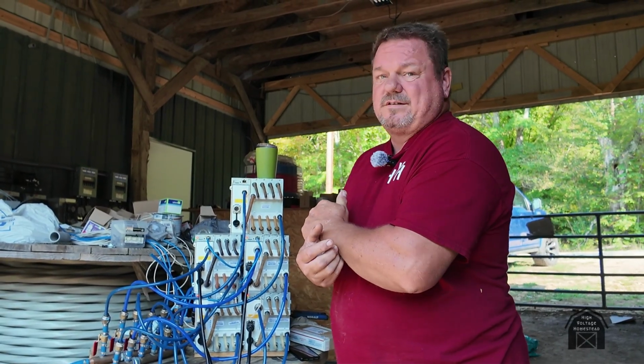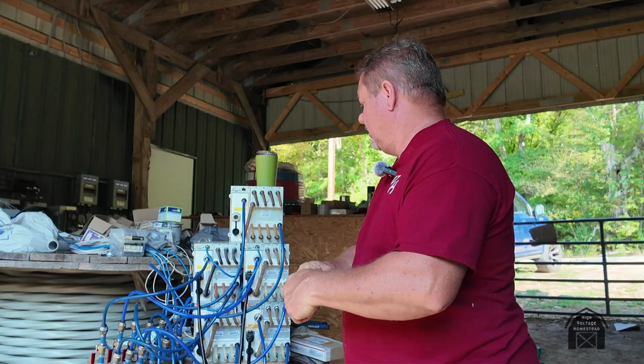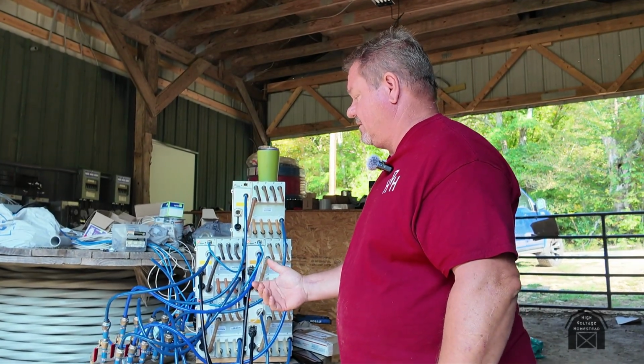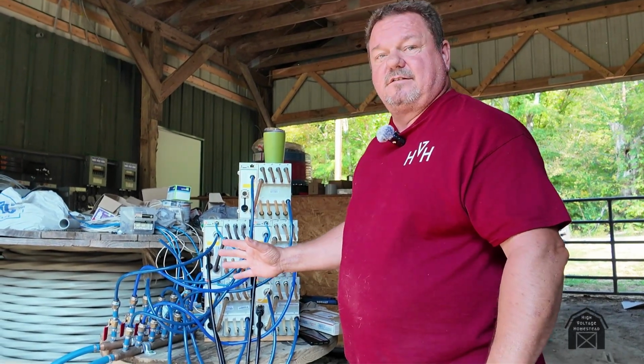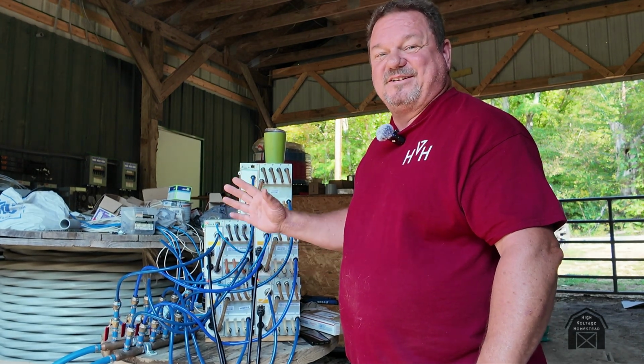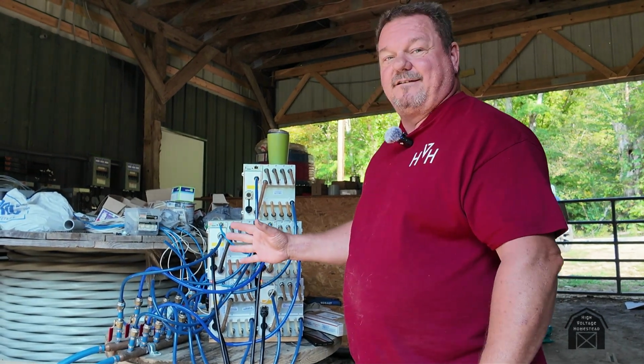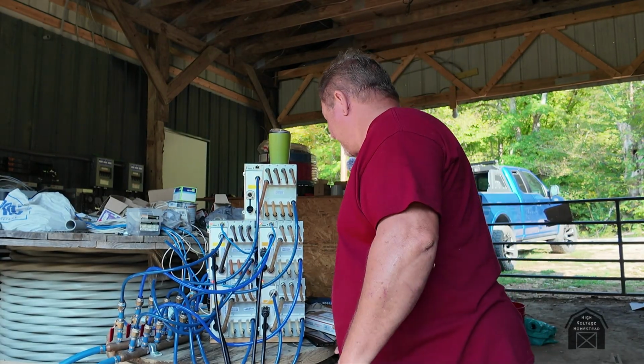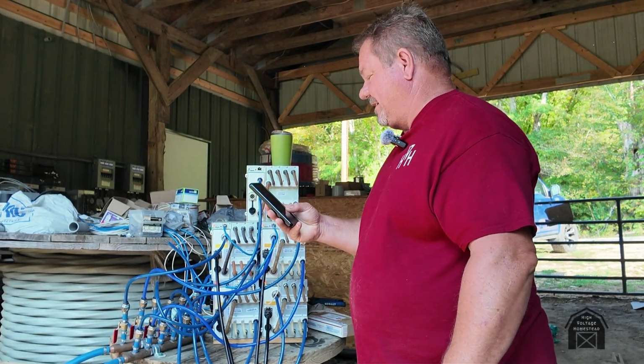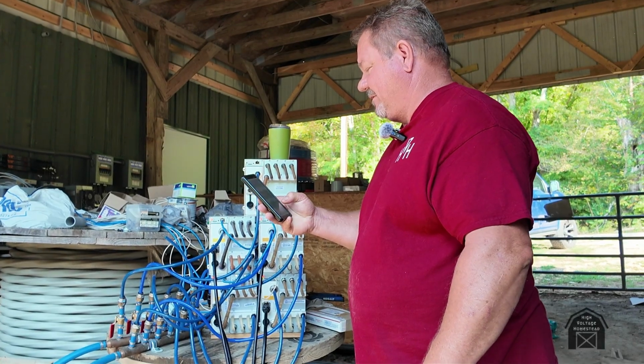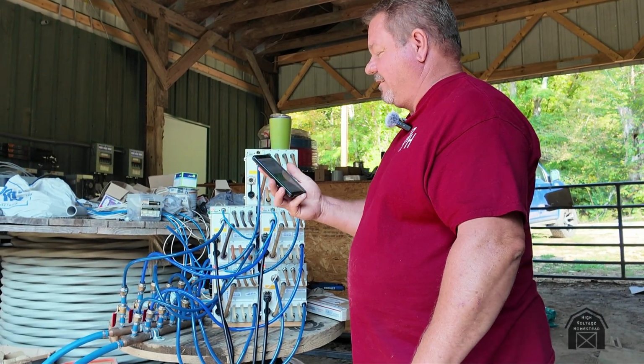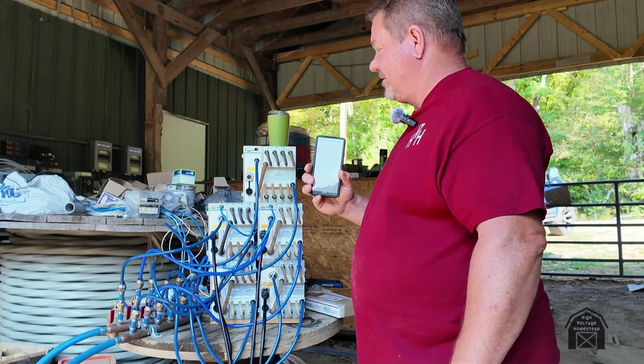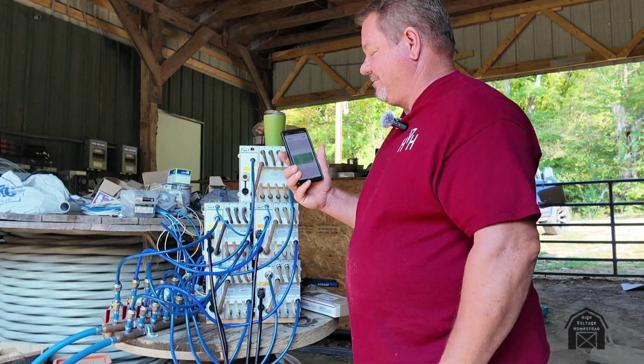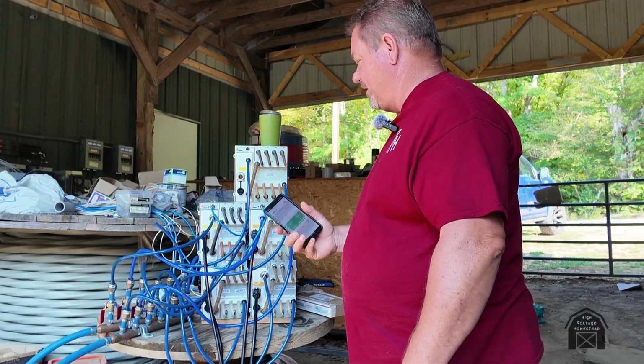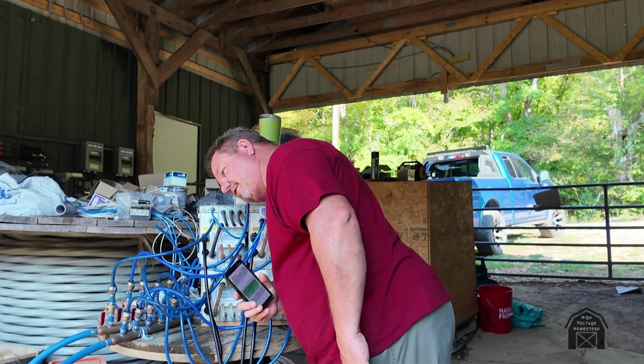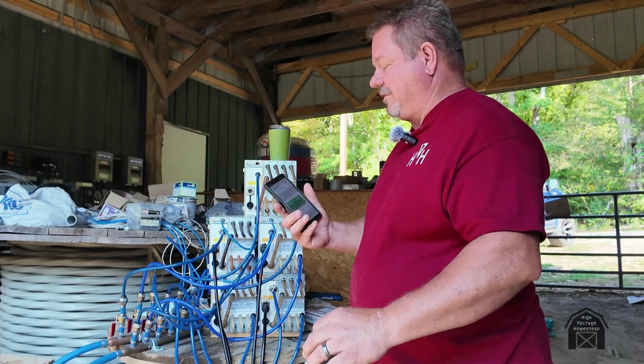But these little guys set out here, it's really awesome. You notice you don't hear nothing - they're running full bore right now. It takes them a minute to get completely started up, but right now we're pulling 23.6 amps on those machines, and they're just silent. You don't even hear the pump running. If you get real close, you can hear the water moving through them just barely.